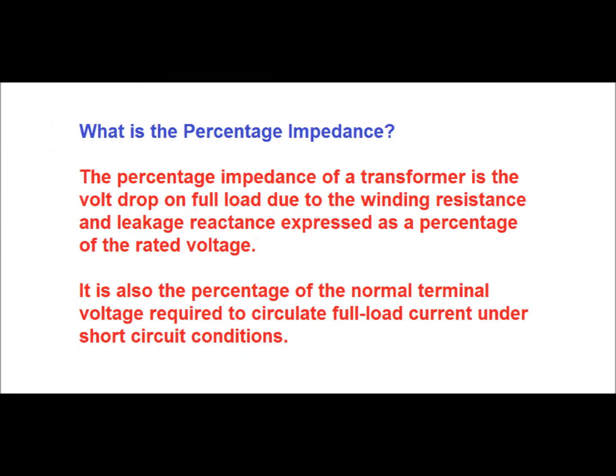What is the percentage impedance of a power transformer? The percentage impedance of a transformer is the voltage drop on full load due to the winding resistance and leakage reactance, i.e. impedance of the transformer, expressed as a percentage of the rated voltage. Alternatively, it is also the percentage of the normal terminal voltage required to circulate full load current under short circuit condition.